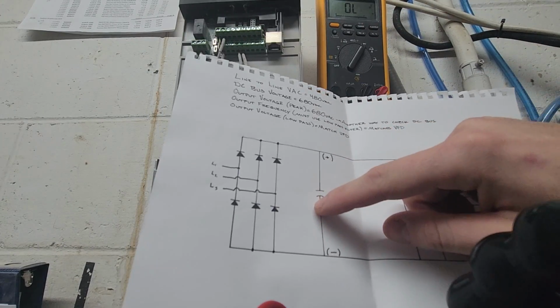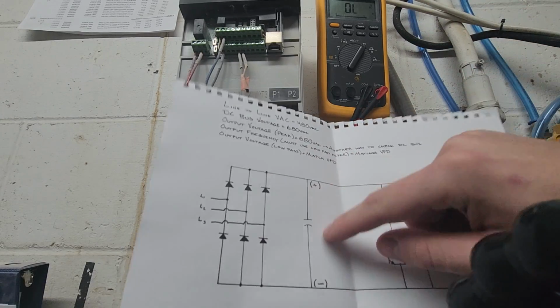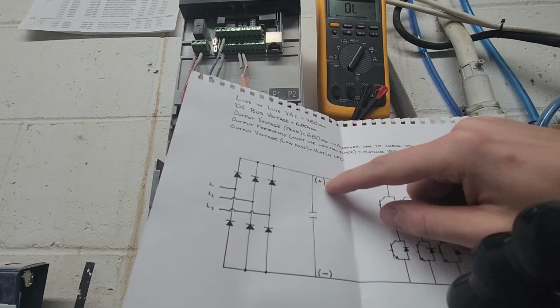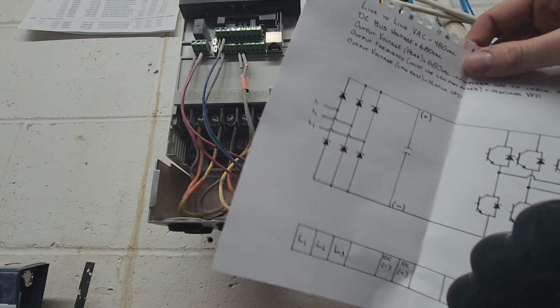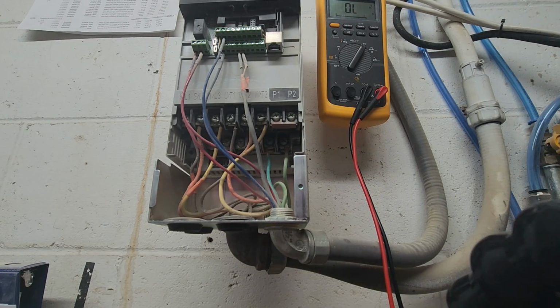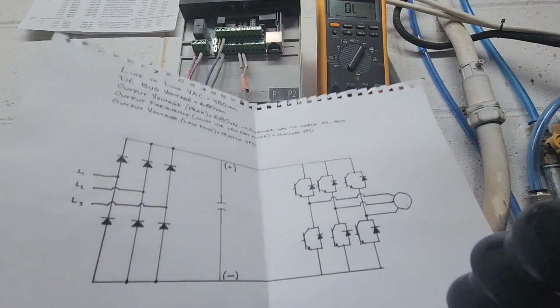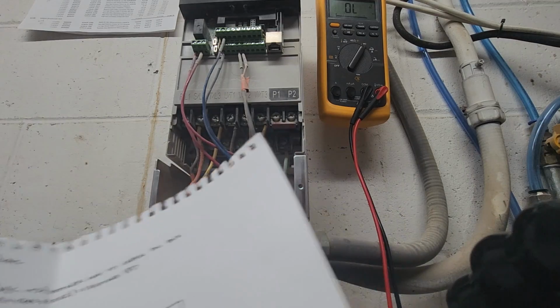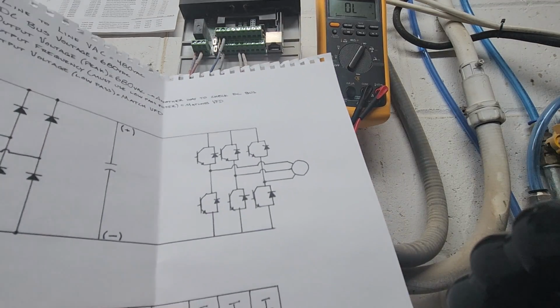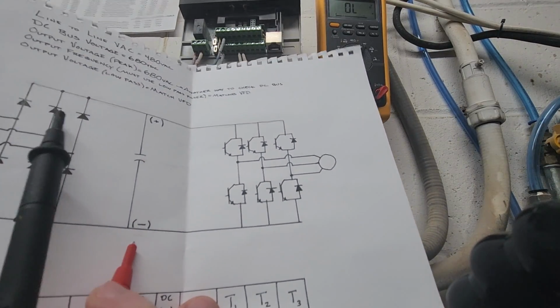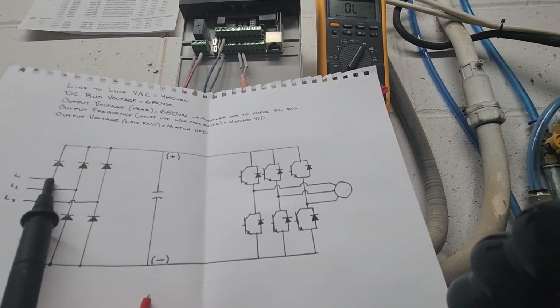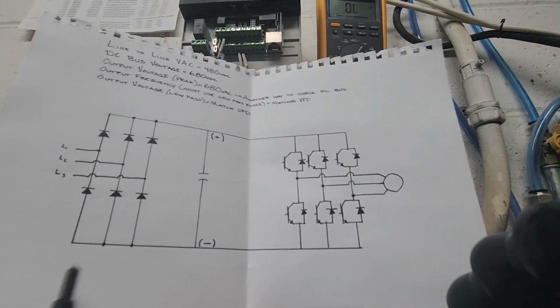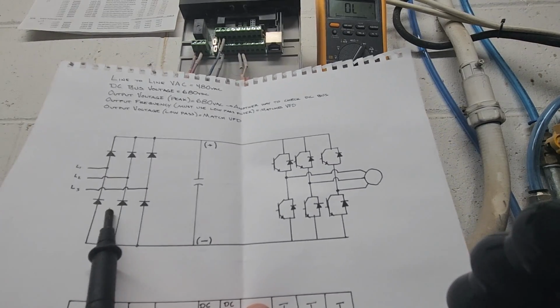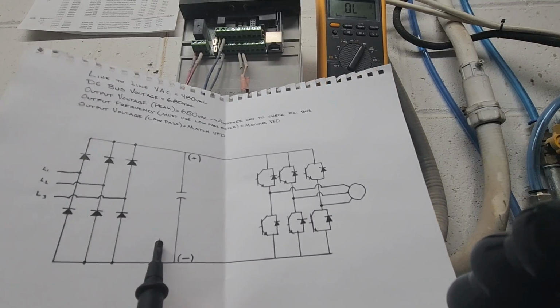Even though it's a smoothing capacitor for DC current, your multimeter isn't going to be able to push anything through this capacitor, so you can basically ignore it as a non-existent feature when we're doing voltage or diode tests. So next thing we're going to do is take our positive probe and put it on our DC bus negative, and we'll put our black probe on L1, L2, and L3, and we'll be checking these bottom 3 diodes here, and then we'll do it in reverse just to make sure that we don't get electron flow back the other way.